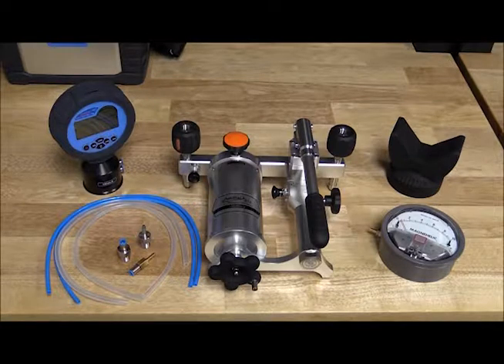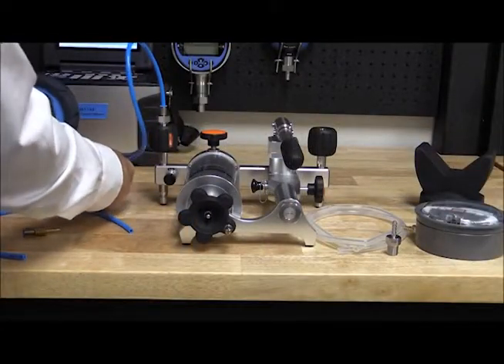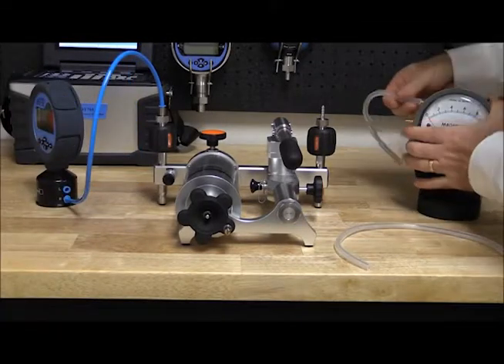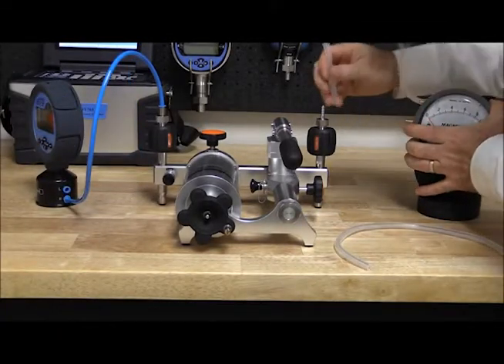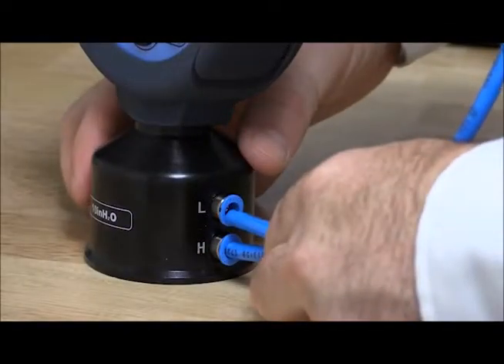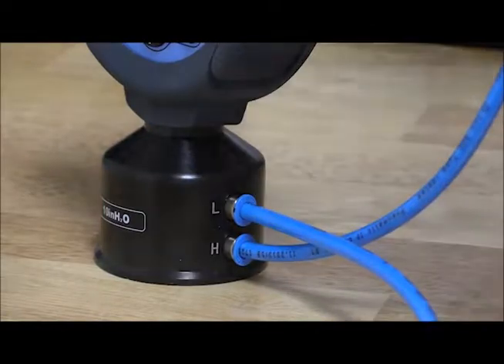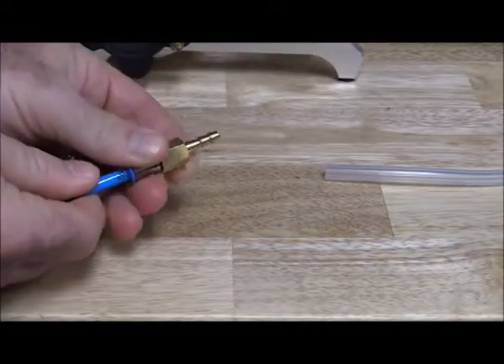In this example, we use an Additel 912 pump to generate the pressure. The 901 pump could also be used. However, the 912 is better able to handle higher ranges and higher volume instruments for this type of setup. The Additel 681 differential gauge will be used as our accurate reference, and we'll be calibrating a Magnehelic differential pressure gauge that is 0 to 10 inches of water. For this method, the high ports of the reference and the DUT are connected to the 912 pump. The low port of the reference gauge and the DUT are connected together, which greatly reduces the influence of environmental errors.